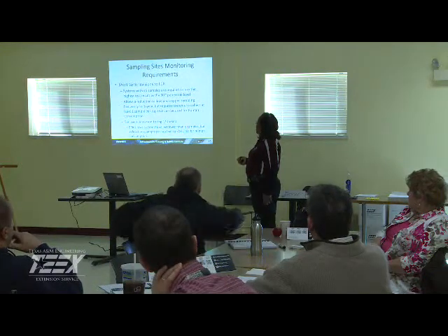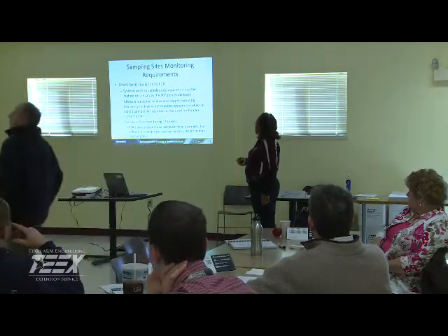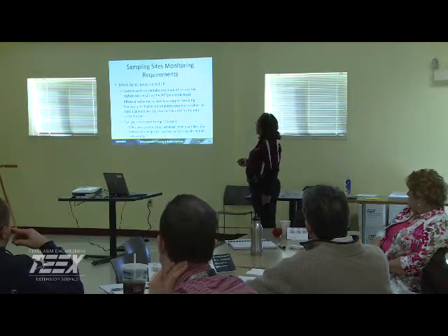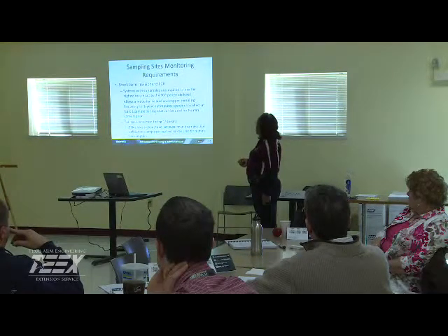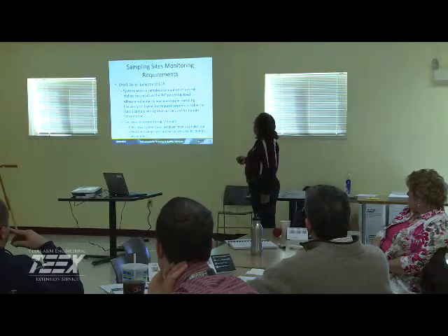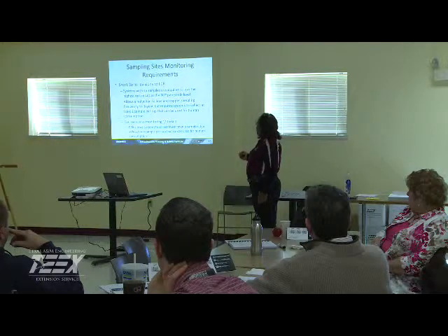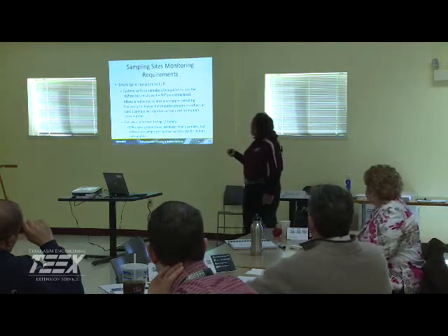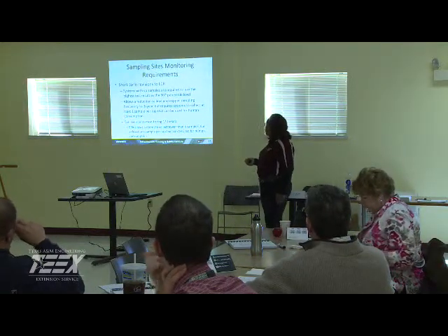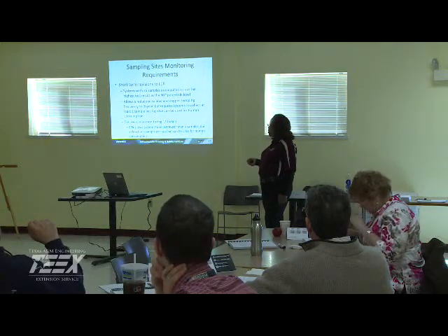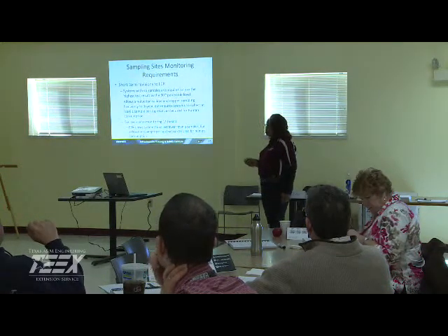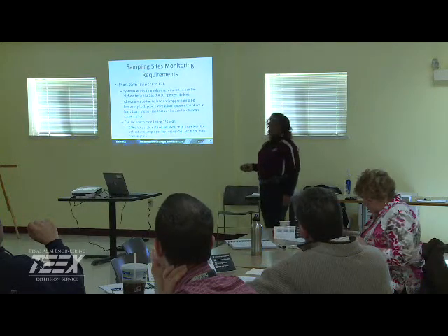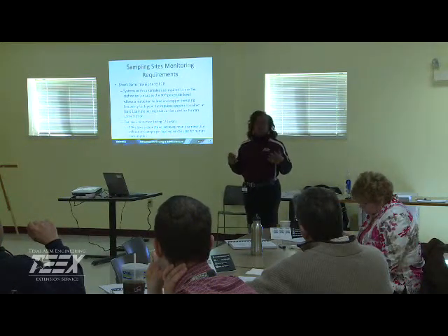Systems with less than 5 samples are required to use the highest test result as the 90th percentile level. And also, another short-term revision allows a reduction in lead and copper sampling frequency to 1 per year, but it requires the system to make sure they're collecting at least 1 sample per tap that can be used for human consumption. You can also have a further reduction to once every 3 years. EPA will allow the system to collect fewer than 5 samples, but again, you've got to go to each tap that is used for human consumption.